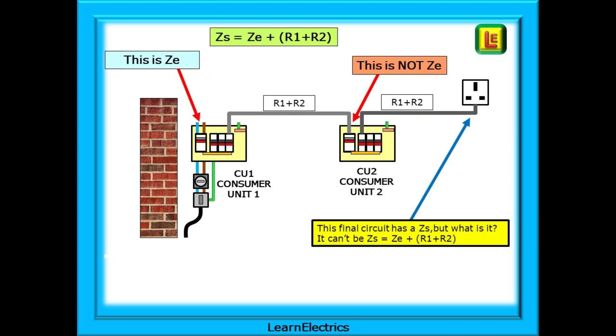ZS is ZE plus R1 plus R2. But now we have two circuit cables, each with their own resistance value. ZE is way back at the incoming position at the main switch of CU1. So the main switch of CU2 cannot be ZE as well. And ZS is used for the end of the circuit, and CU2 is in the middle of two circuit cables. So what can we do?